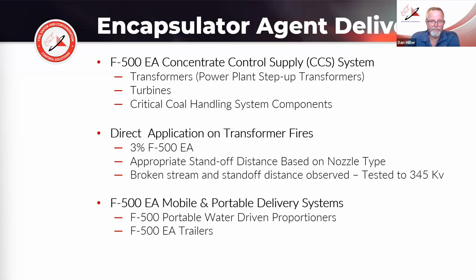If you're doing manual firefighting, as long as you maintain that appropriate standoff distance and use a broken stream nozzle, you don't have that current flow back to the nozzle. And if you're using FM nozzles, an FM nozzle is a fog nozzle, all brass, that won't go to a straight stream. It's always a broken stream. And then we have mobile and portable delivery systems as well. We have portable water-driven proportioners and encapsulator agent trailers. So you can attack a transformer fire, for example, anywhere on your site or at substation sites as well.